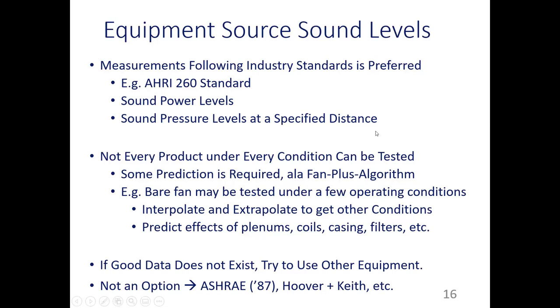But usually things don't work out that easily. Usually they'll give you sound pressure levels at 30 feet for some rooftop unit, but you need to find it for 4 feet away because it's going down to the roof of a building. You'll have to calculate back to get that. You should know how to do that at this point. One other thing I'll say is manufacturers can really make their data confusing. I think a lot of times they have somebody doing it who maybe knows enough to be dangerous, but that's about it. You'll get a lot of data where, just from the way they label it, you don't know if they even know the difference between sound power levels and sound pressure levels, and A-weighted and non-A-weighted. So it can be quite confusing. It might be a 1,000-person company, and you might need to call in and get a hold of that one person there that actually knows. They might not have one person that knows.